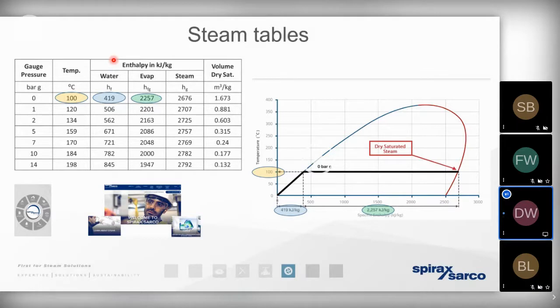We can also call it the enthalpy of water. The next column, that shows us what we refer to as the enthalpy of evaporation, which we also refer to as the latent heat. That's the energy that we need to put into that boiling water to enable it to fully evaporate and produce a mass of steam. So if we add the two together, we then get the total heat present in the steam. And the final column, it tells us that if we know the pressure that the steam is being generated or distributed at, then we know the volume. And as you can see, if we increase the pressure, then all of these values are changing from the temperature to the energy that's present to the volume.